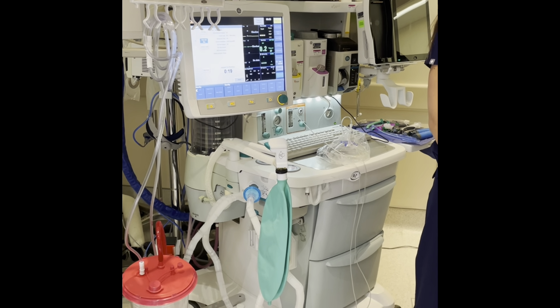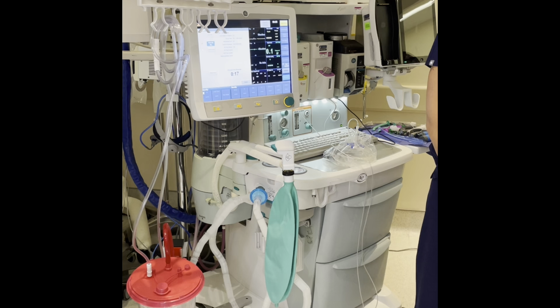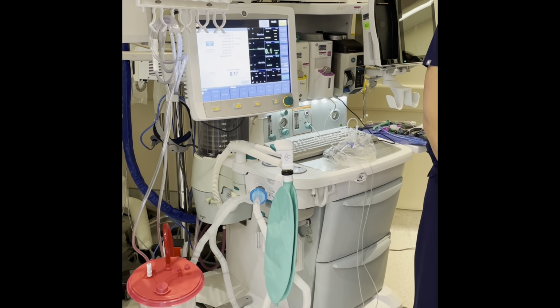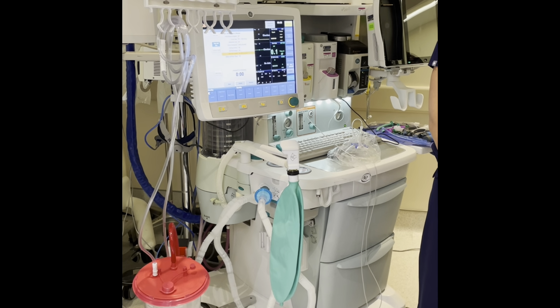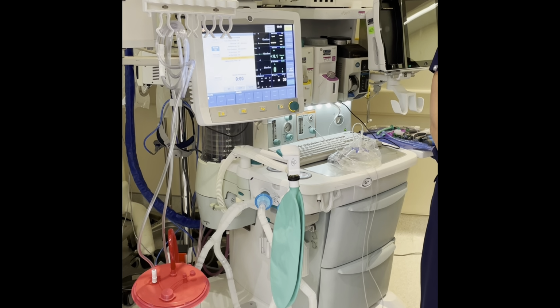It's checking the breathing system, the internal system of the machine. It's checking that there's no leak, that the flow sensors are working well. It's telling us there's no N2O pressure because we don't have N2O pipe pressure in this room.